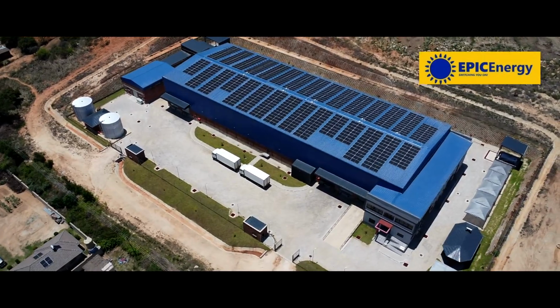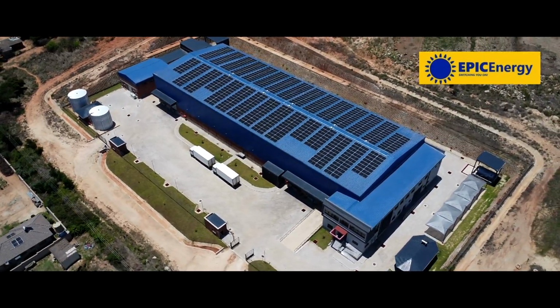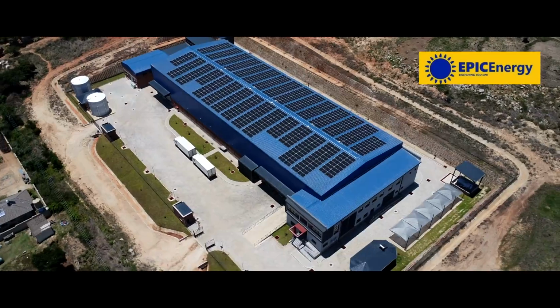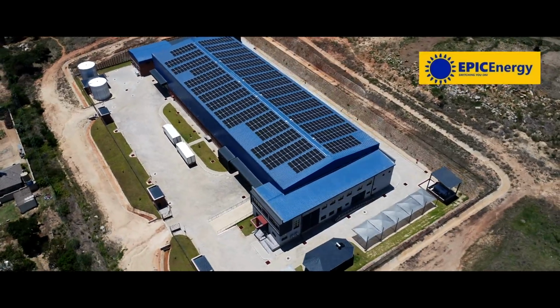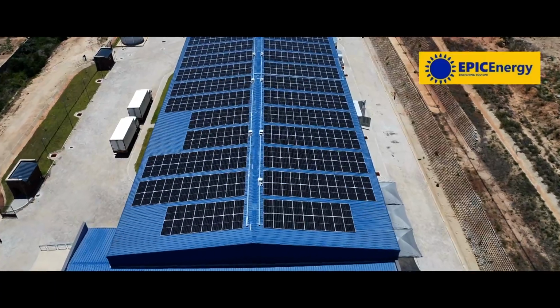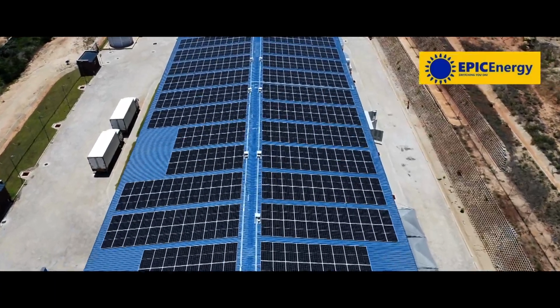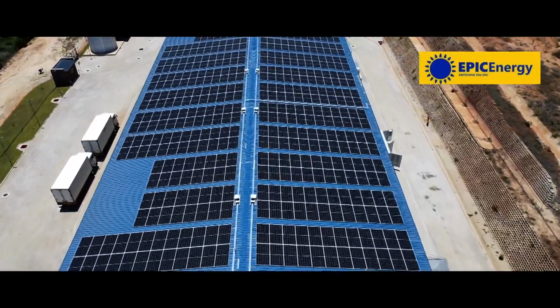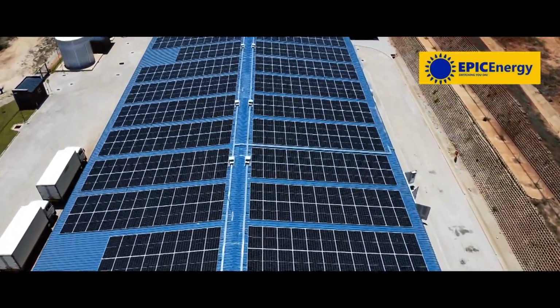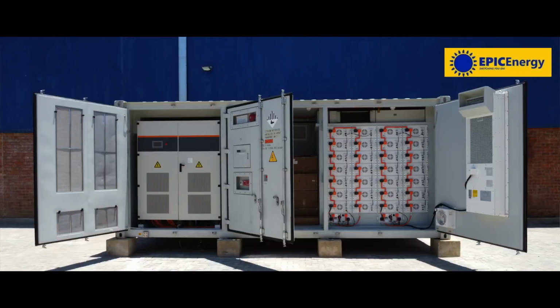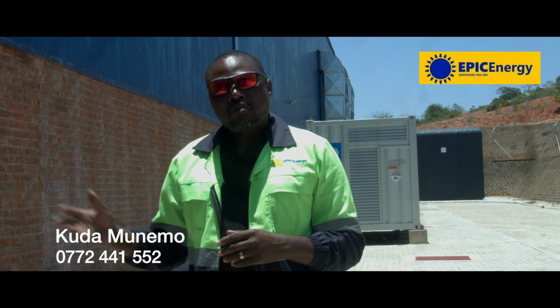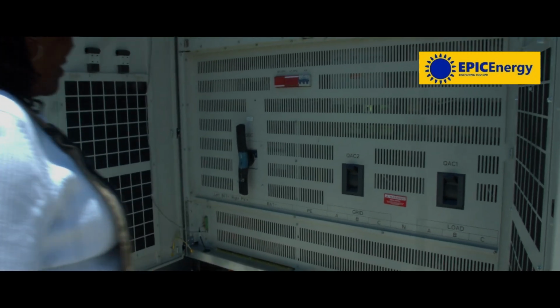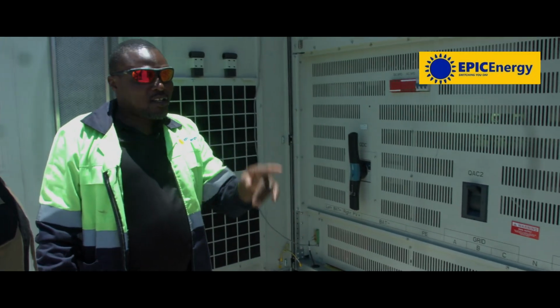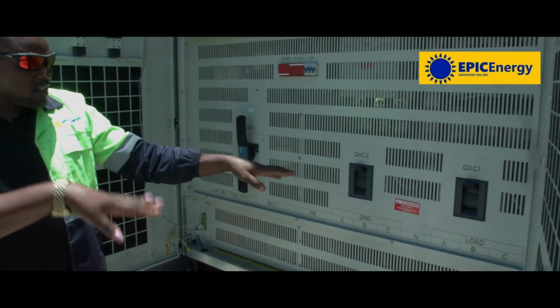We are here in Mutare where we have installed a very big system which is powering a massive warehouse where I'm standing right here. This system is a 370 kilowatt solar array with a 500 kilowatt inverter capacity and an 802 kilowatt hours battery bank, which is a massive battery bank for evening use when there is no power or there is no grid. So I just want to take you through this particular setup which we have done here in Mutare.